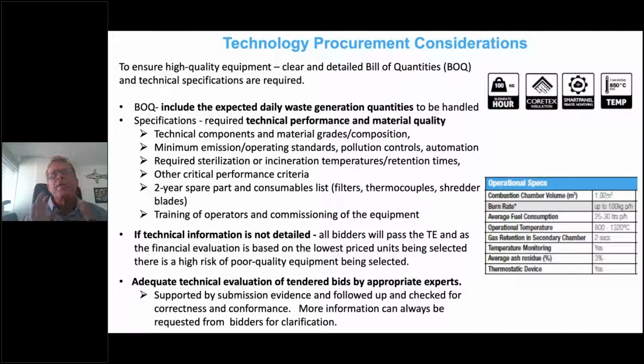And not only are the specifications important, the actual technical evaluation of the bids that come in is critically important. Ideally you should get the people who are preparing the specifications to do the actual evaluations of those bids, because they wrote those specifications and they understand the levels of material performance or quality. Normally tenders come in and they send a bunch of information, but it needs to be painstakingly filtered through to make sure that all of the things claimed by the manufacturer of these pieces of equipment are checked for correctness and conformance.